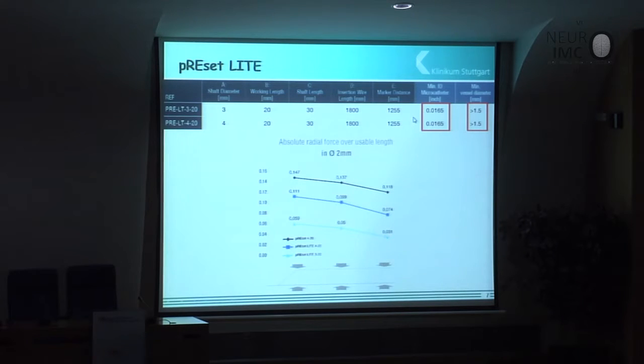Another difference is shown here. This is the radial force curve of the regular device. This is for preset LT 4x20 and for preset LT 3x20. As you see here, the radial force is significantly lower for the LT version than for the regular version. This is very simple to understand. What is the background? To make the device accepted by a lower profile microcatheter, you have to make the struts thinner. If you make the struts thinner, the radial force will be lower as well.